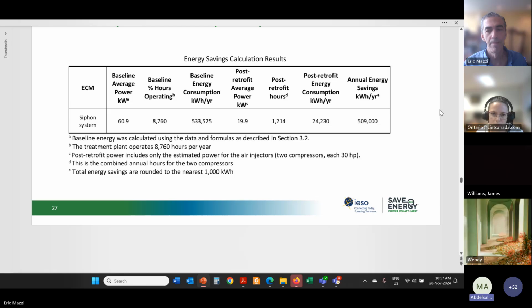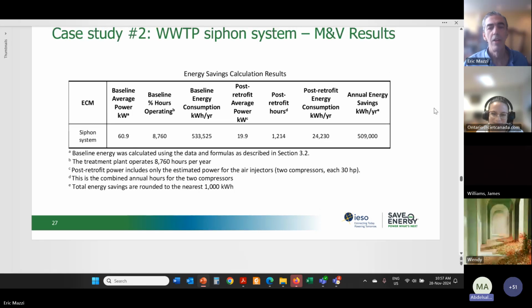And these were obtained from measurements or from calculations? The post-retrofit from measurements. So in this case, I'm curious to learn, from the standpoint of option D, does it have to be calibrated model minus calibrated model, or can it be a mix and match if the case allows? Well, technically I guess I would argue it's a calibrated model of the pumps, but it's really a philosophical point. There are no pumps, so my modeled consumption of 0 has to be correct.